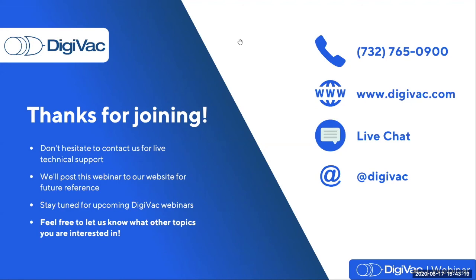We have another question from Paul. Just real quick before I continue with my wrap up, have you had any issues with filament corrosion? This happens not as a result of cleaning, we've found. As a matter of fact, we recommend frequent cleaning in order to prevent filament corrosion. We typically have seen corrosion of filaments in super dirty processes where the sensor has maybe been allowed to sit without cleaning for a large amount of time. For instance, we have a customer who typically works with food processing where they do a lot of freeze drying. Sometimes those sensors will be left to sort of marinate in their own contamination over time.